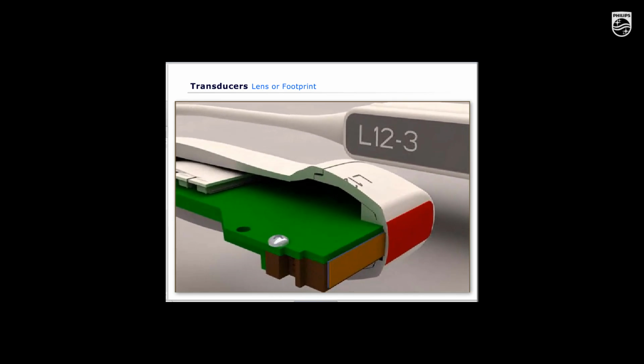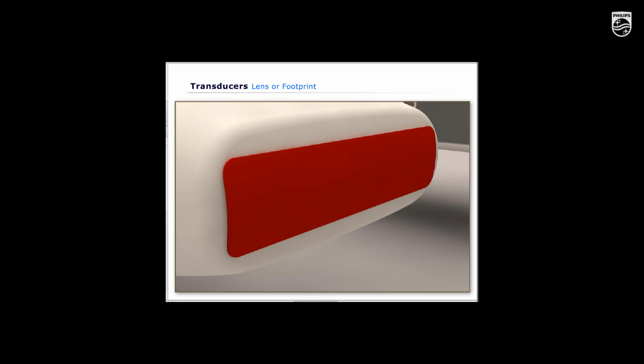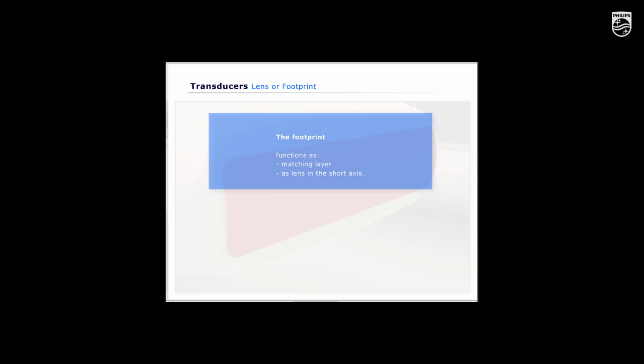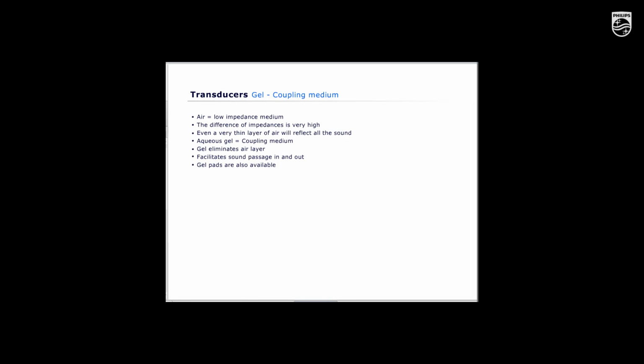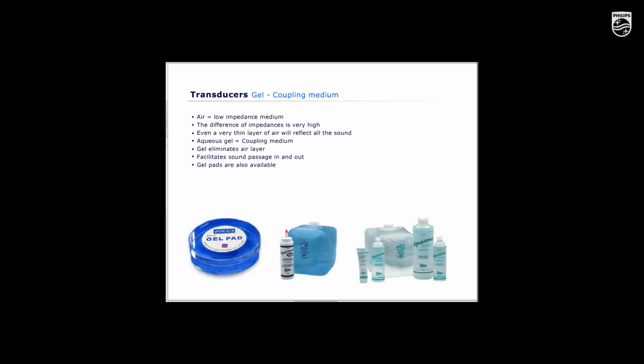The lens or footprint is the part of the transducer that contacts the patient. The footprint functions as a matching layer and as a lens for the short axis. Because of its very low impedance, even a thin layer of air between the transducer and the skin surface reflects virtually all the sound, preventing any penetration into the tissue. For this reason, gel is used as a coupling medium. This eliminates the air layer and enables efficient passage of the ultrasound into and out of the tissue.